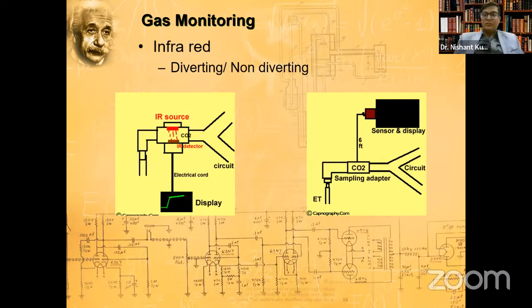the concentration or the partial pressures of the gases inside the breathing circuit. Now, this is the most common one and the most adaptive. Remember, infrared produces heat, so if you feel the mainstream sensor, it will always be warm. It can cause burns and other injuries, which you have to be careful of. Now, if there is dirt, mucus plugs or any organic matter on those two circles, you'll get a different reading and your reading won't be accurate. Another problem with infrared is that nitrous oxide interferes with the detection of CO2. Most of the newer machines have an auto nitrous oxide corrector.